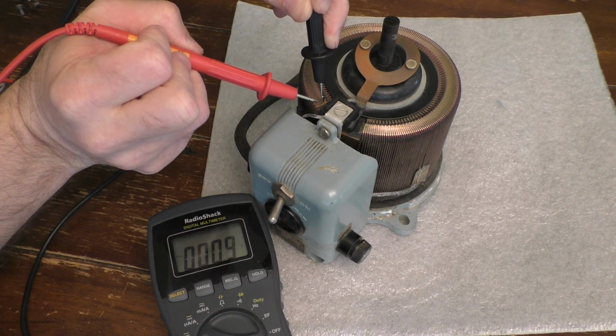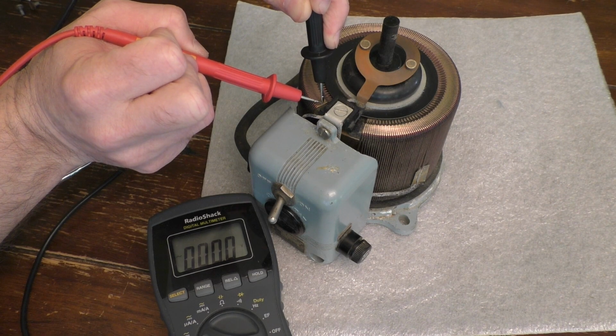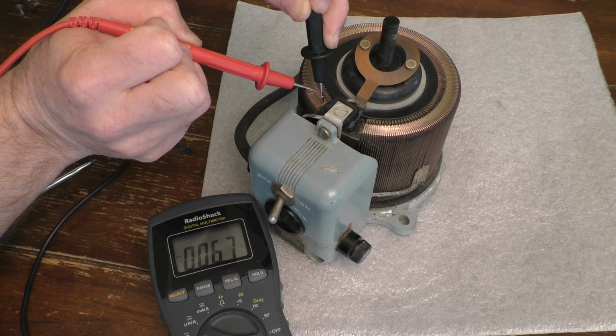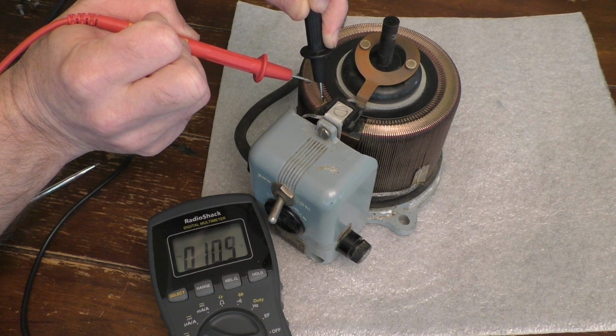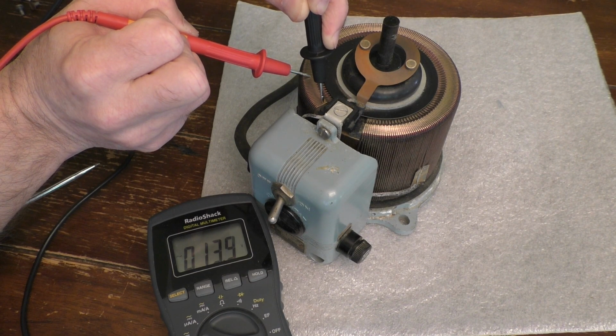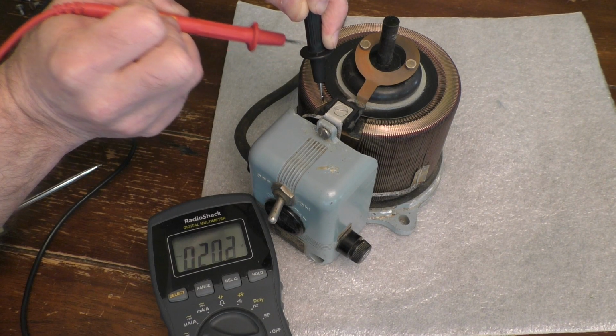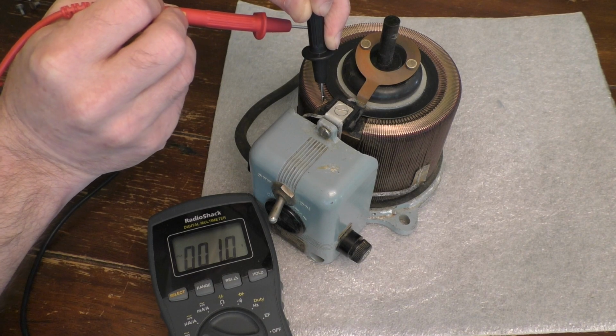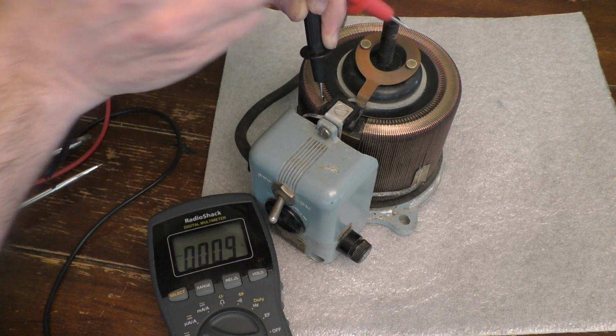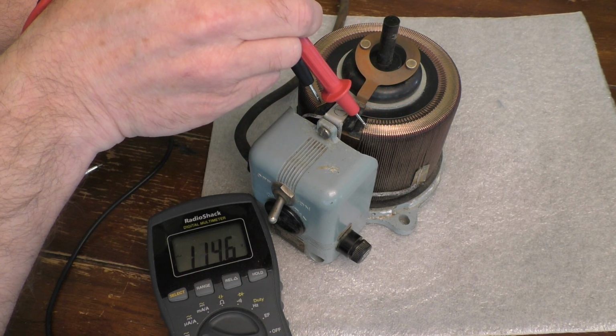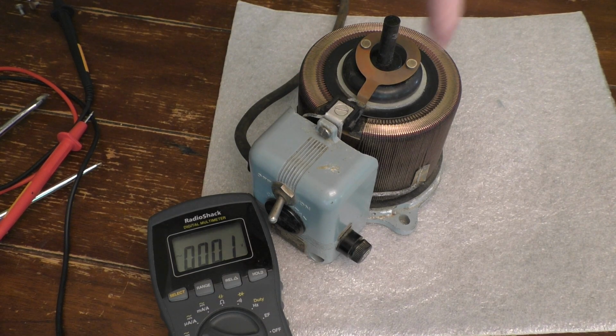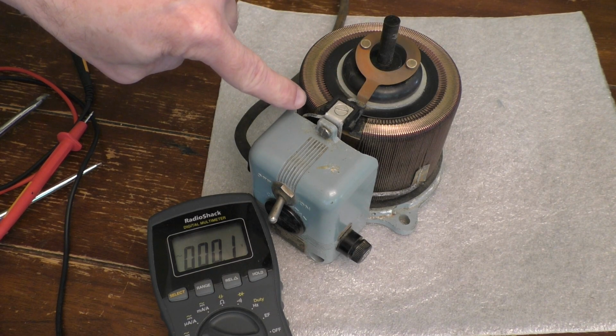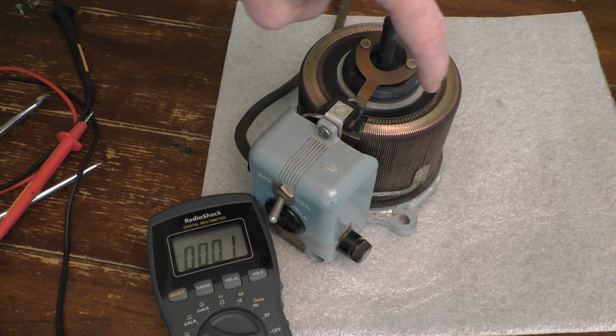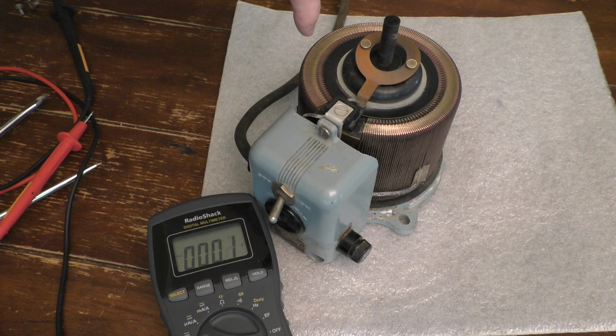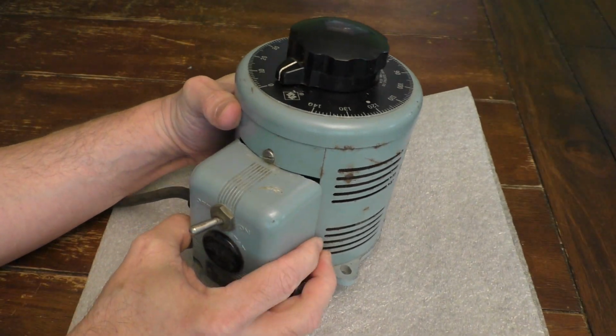But now if I were to move up the winding from 0 volts, as I go up, the red lead is starting to see higher voltage. And as I go all the way up to the 120, you will see it just increasing all the way to 120. So as I go up the winding, I'm increasing the voltage to the maximum voltage of the 120. And I could also step up all the way to 140, all the way up to here. And so that's basically how this is working. You set a neutral point here and a 120 volt point here, and then anywhere you tap into the coil along the line is just a fraction or percentage of that voltage. And there you go. That is how a variable auto transformer works.